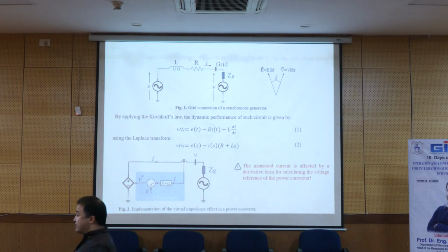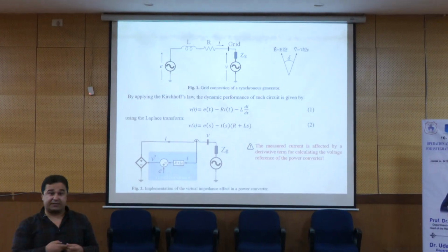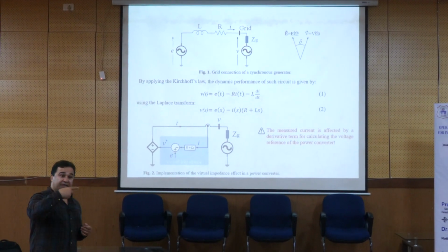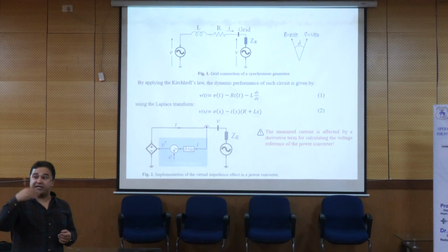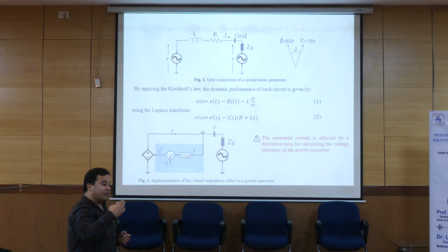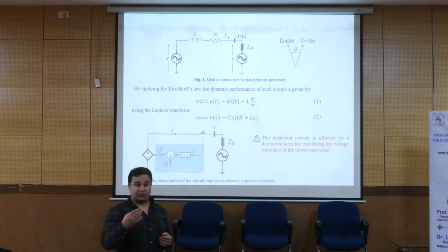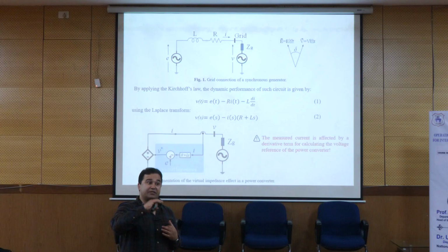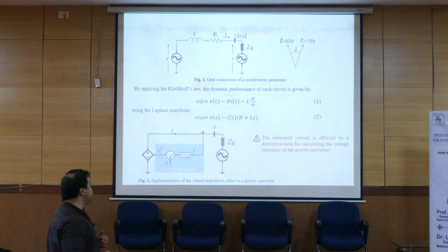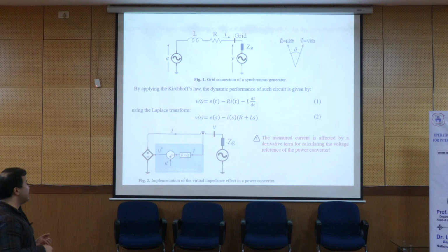So when we pass through this derivative part, in fact, we get the derivative of these disturbances and increase the value of the disturbances in the power grid. So in fact, we inject disturbances to the power grid. So in this case, we change the equation. Instead of following the voltage, we just transfer this one to here.